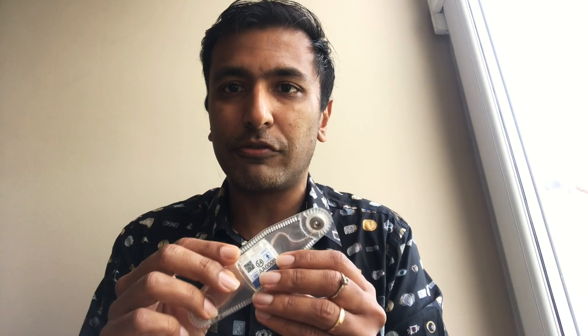Because there is a button on the device, when the patient experiences something they can press it, which puts a little marker on the continuous recording allowing the doctor to focus on those areas — particularly useful. In addition, the device comes with a diary so the patient can record what they're experiencing and when. Once the recording time is over, the patient simply takes the patch off, puts it back in the box it came in, and posts it back. The device reaches a central location where the information is downloaded; a physiologist then reviews all the data, identifies incidental rhythm disturbances and patient-triggered events, compiles a report, and sends it to the cardiologist, who contacts the patient to discuss results.